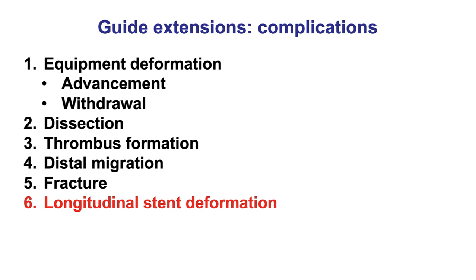In summary, guide extensions have been a revolution for contemporary PCI. They are used very often, most commonly to facilitate delivery, but also when there is a complication to facilitate retrieval or to facilitate angiography. The key thing is to put the pushrod under a towel to avoid wrapping of guide wires with the pushrod. It is also important to monitor equipment going in and out because if they catch the collar, equipment damage can occur. Very meticulous use of guide extensions, advancement in the coronary using the inch-worming technique in a gentle and closely monitored way, can allow excellent use of those devices to improve outcomes and minimize potential safety concerns. Thank you very much.